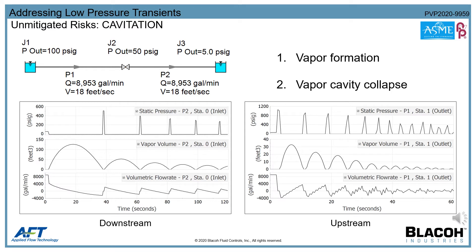A second risk of unmitigated low pressure transients is cavitation. Cavitation is a general term encompassing two effects: first, vapor formation, where liquids vaporize as the system pressure falls below the fluid's vapor pressure; and second, vapor cavity collapse with the returning pressure wave or flow reversal. A collapsed vapor pocket can be an extremely violent high-pressure event, damaging the site of cavitation and propagating additional high-pressure transient waves.